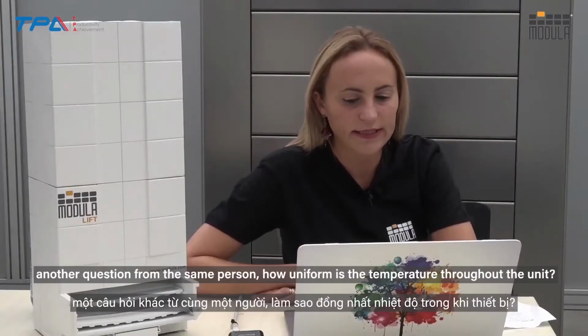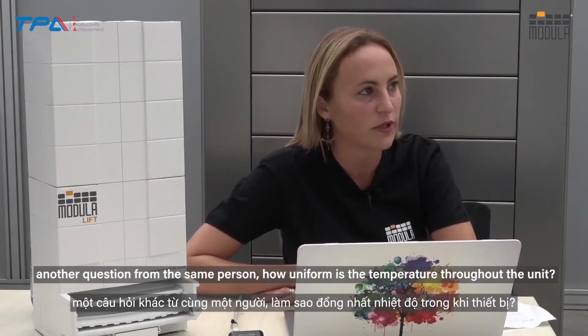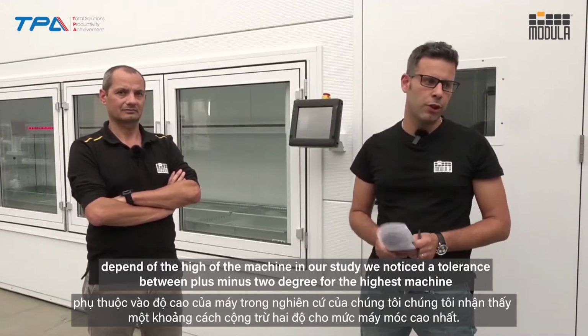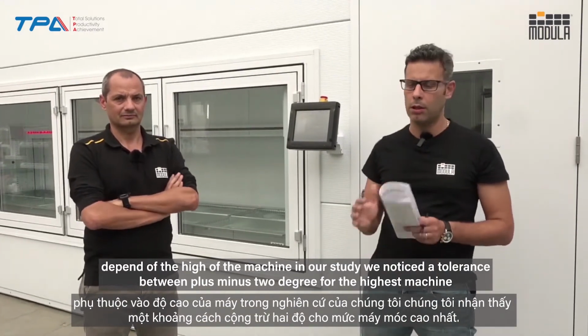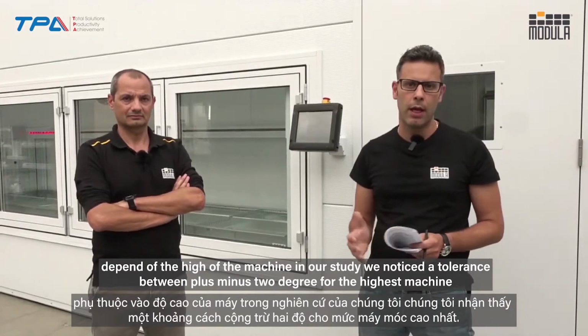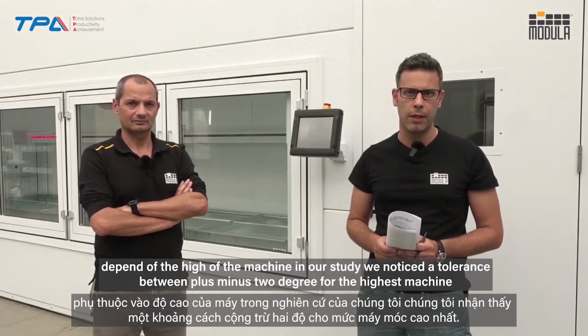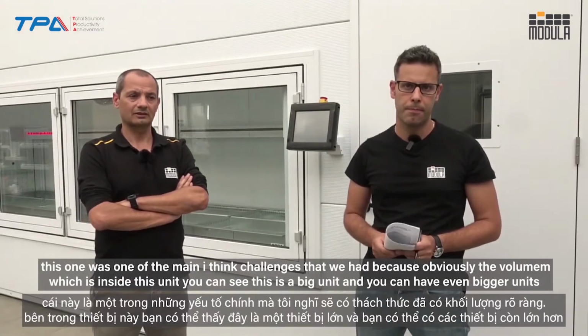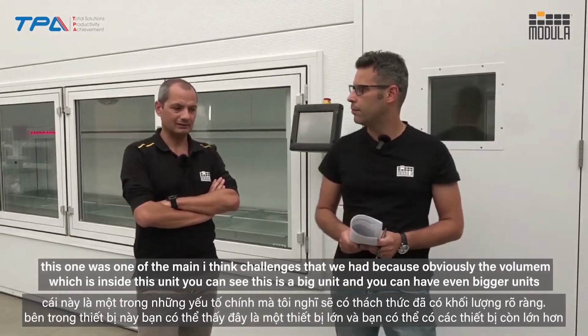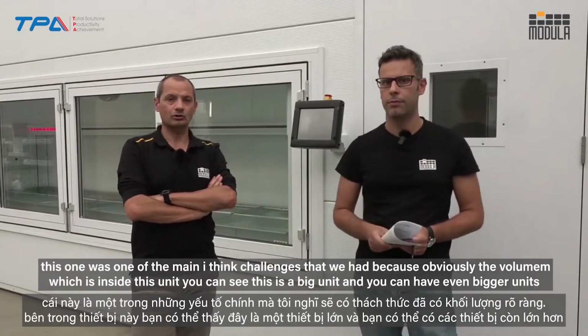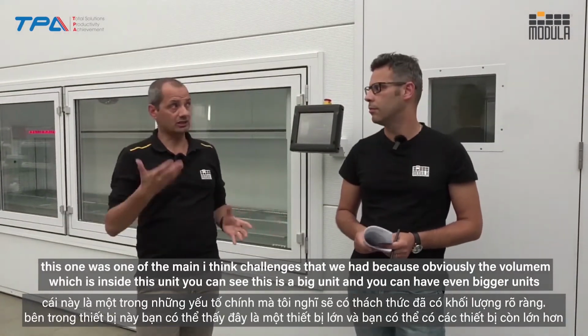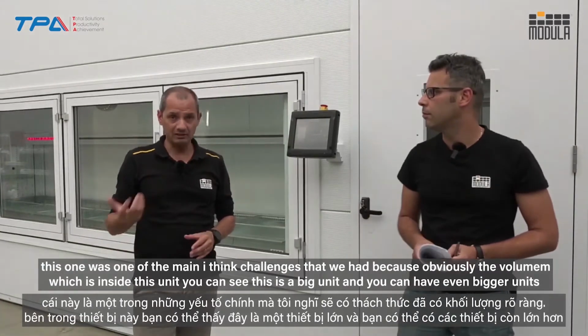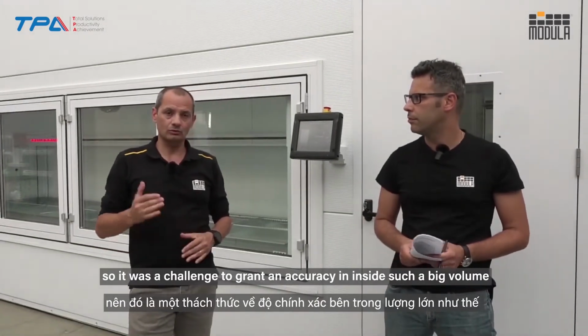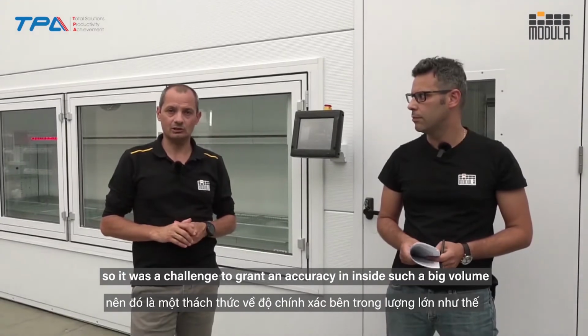Yes, absolutely. Another question from the same person: how uniform is the temperature throughout the unit? Depends on the height of the machine. In our study, we noticed a tolerance between plus minus 2 degrees for the highest machine. This one was one of the main challenges that we had, because obviously the volume inside this unit, you can see this is a big unit, and we can have even bigger units. So it was a challenge to grant an accuracy inside such a big volume.